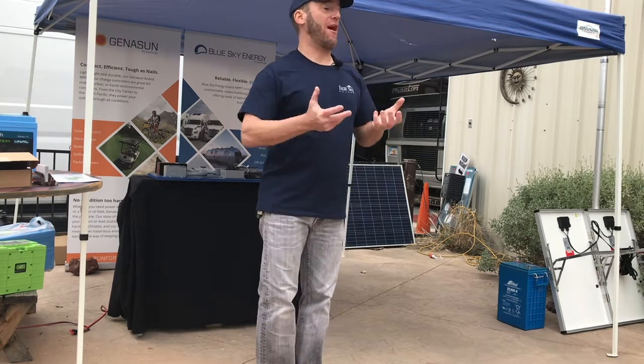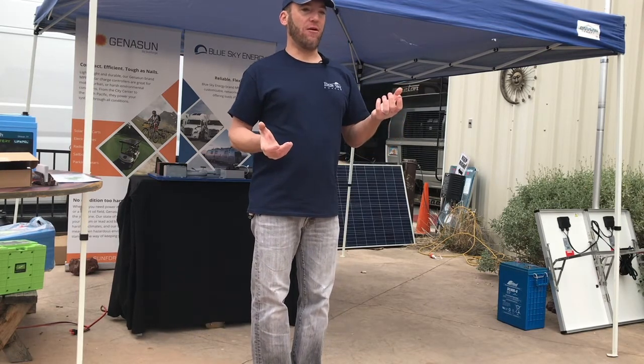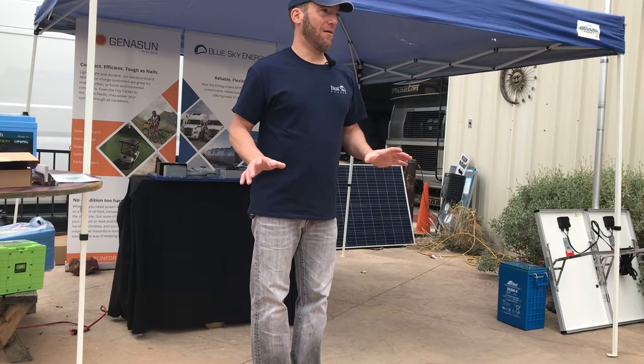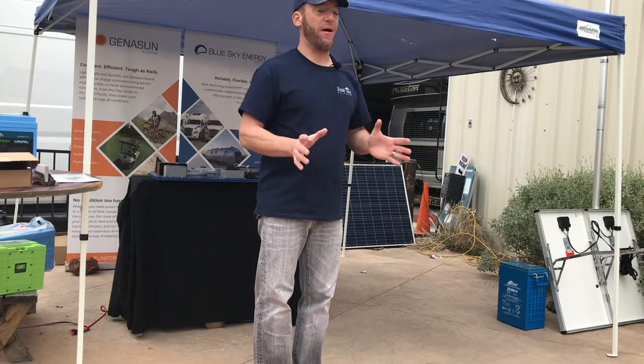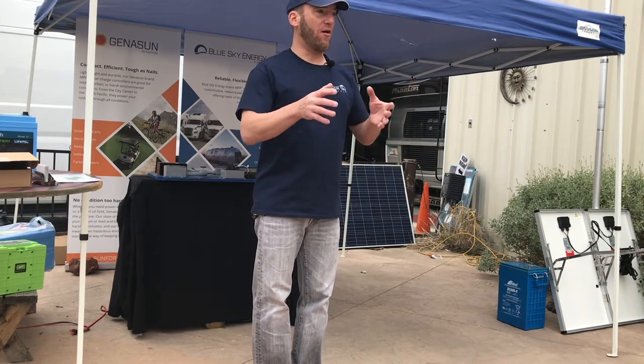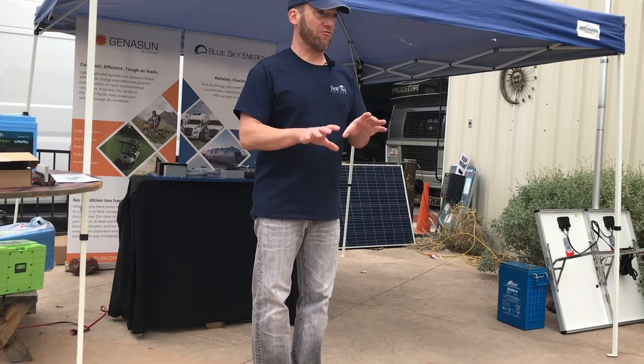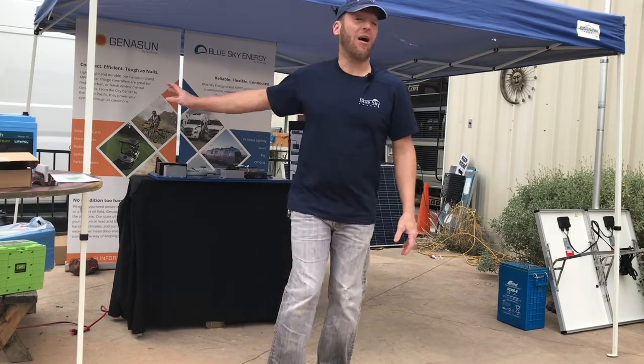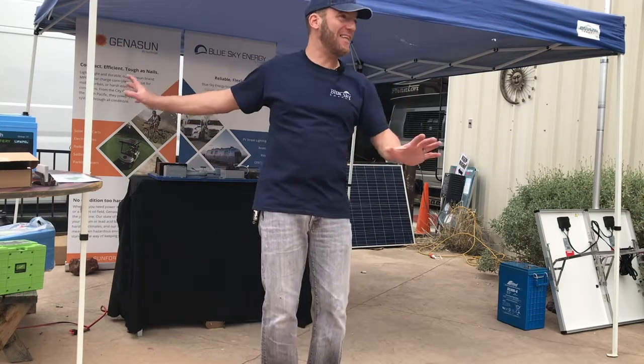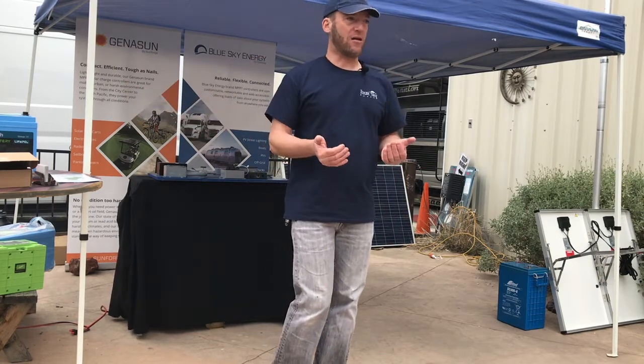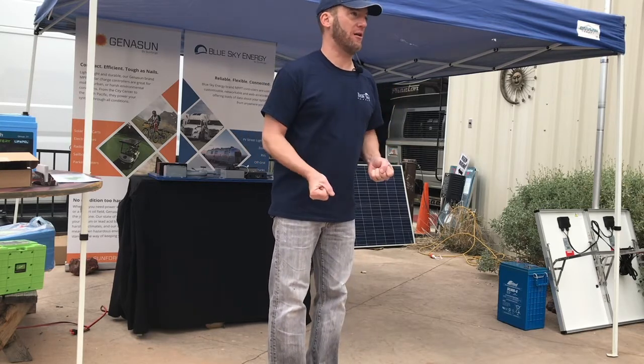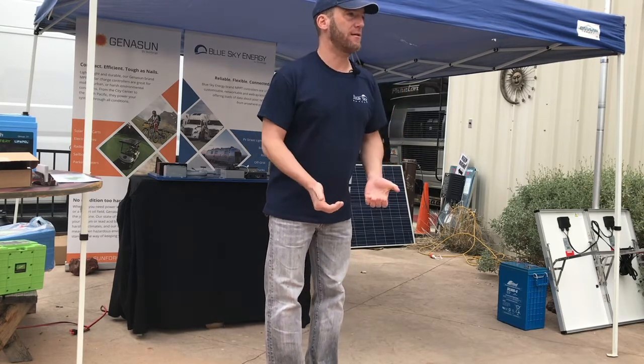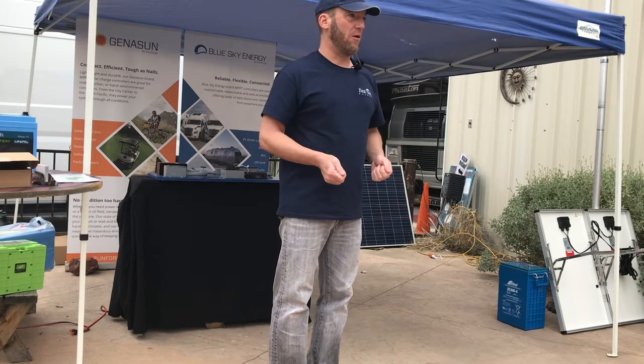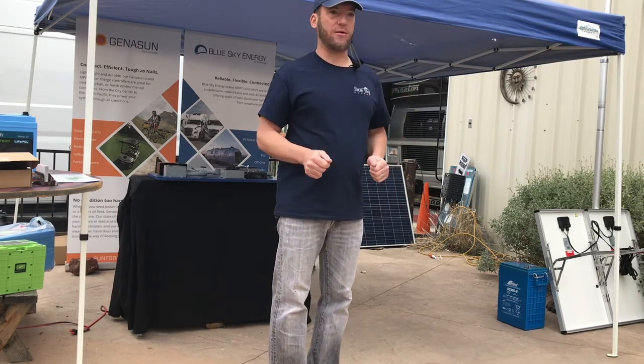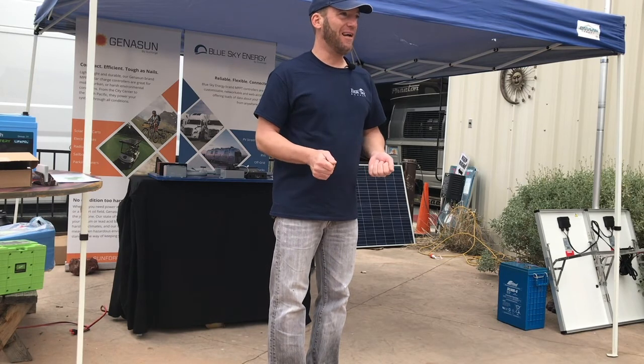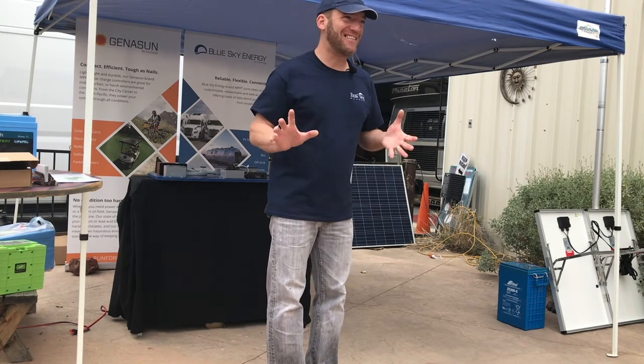Think of voltage as pressure, okay? In just about any solar system in the world, if the input voltage is below 15 volts, something's wrong. I mean, maybe in some conditions you're down to 14 and a half or 14—I can see that happening. But when troubleshooting, I get calls all the time like, hey Ryan, my controller isn't charging, or it's charging at a very low rate. The first thing I have them do is check their input voltage, either on the Pro Remote or physically with a voltage meter. And if their voltage is under 15 and it's not raining or lacking sun...